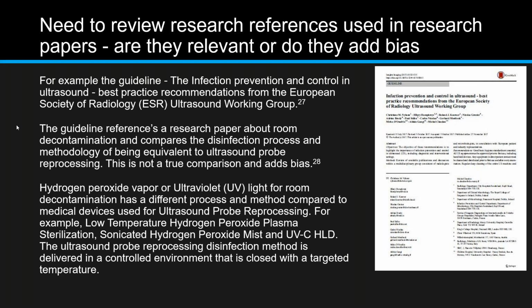Hydrogen peroxide vapor or UV light for room disinfection has an entirely different purpose and methods compared to ultrasound probe reprocessing. The probe reprocessing disinfection method is delivered in a very controlled, closed environment where distances are not measured in meters, but in millimeters or centimeters. And since intensity falls off as the square of distance, it's totally different. So one can't look at the data for disinfection of surfaces and make any conclusions about the use of a closed area for disinfecting probes, and the reverse is true. The data needs to be reviewed separately, analyzed separately. Next slide.